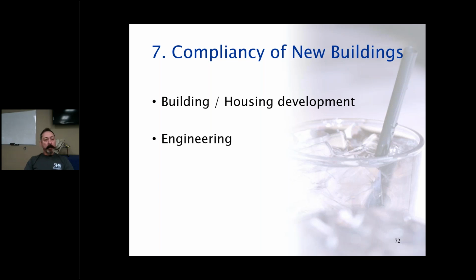Is it going to go inside the building? Is it going to go at the property line? Does it have to be in a vault? Well, then now that's a confined space. And so there are all these challenges that go around installing a backflow preventer for premise isolation. So engineering should be involved in some of these decisions on where they're going to go. Remember, an RP cannot be in a pit, so that one would have to be an above ground heated enclosure. So all these challenges go around premise isolation. So engineering diagrams or policies around the CSA B64.10 have to be established and then adhered to in our cross connection control program.